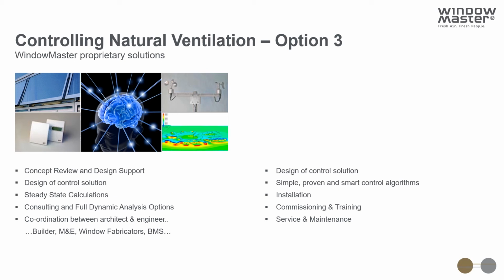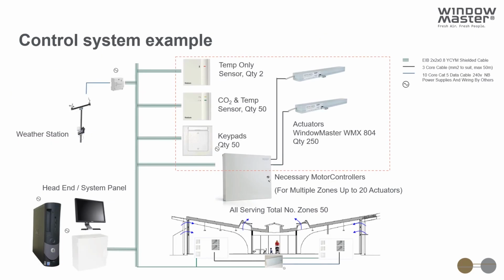We also have the ability to commission, deliver and service those systems as well, either directly or through our installer partners. A typical turnkey system from WindowMaster may look like this, with a number of temperature-only sensors or CO2 and temperature sensors. Override keypads is something that we always encourage, as well as the controllers and the groups of actuators around the building. There would always be a weather station so that we know what's going on outside, and there would be some sort of head end or system panel, which is the brain which will do the decision making on where to send each group of actuators to.